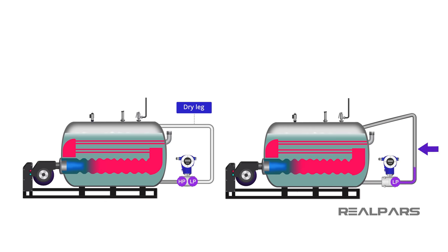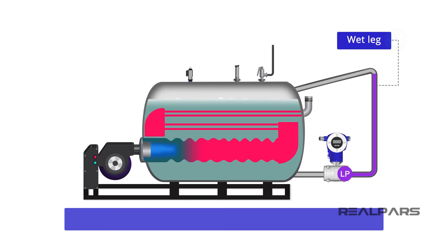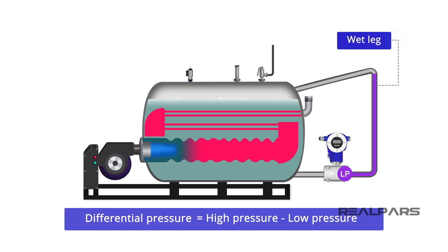Sometimes the reference leg needs to be filled with a fluid — this leg is now referred to as a wet leg. There are many reasons for a wet leg, such as avoiding the error in measurement caused by vapor condensate in the reference leg. The differential pressure, as always, will be high pressure minus low pressure. But the resulting differential pressure is not easy to predict because the liquid in the vessel is usually not the same as the liquid in the wet leg.